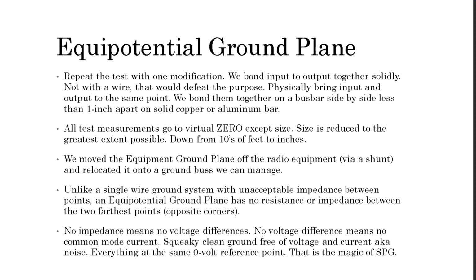And we've reduced the size to the greatest extent possible, down from tens of feet down to just a few inches. What we've done is we've moved the equipment ground plane off the actual radio equipment and all the wiring and relocated it onto a ground bus where we can manage it. We can shrink a big office, say 40,000 square feet electrically, down to just a square foot of a bus bar. Unlike a single wire ground system with unacceptable impedance between points, an equipotential ground plane has no resistance or impedance between the 2 furthest points on the plane or the opposite corners of a bus bar.